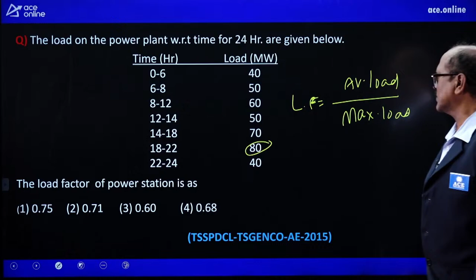So very clearly, it's given as: 6 hours 40 megawatt, 2 hours 50 megawatt - simply 6 into 40 plus 2 into 50 plus 4 into 60 plus 2 into 50 plus 4 into 70 plus 4 into 80 plus 2 into 40, divided by 24 will give the average load. Load factor equals average load divided by maximum load. Average load is calculated by summing 6 into 40, 2 into 50, 4 into 60 and so on, up to the last 2 into 40, total divided by 24 gives the average load we discussed here - not that type, divided by maximum load 80 gives the answer.